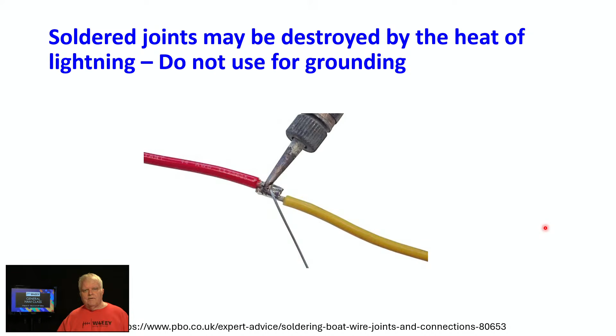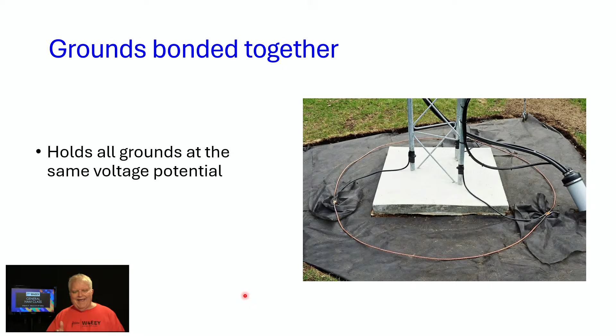Grounds bonded together. Here we have a three-legged tower. Each of the legs goes out to a ground, and there's a ground ring, and they're all bonded together, and there are ground rods at least in 3 spots. We say you want to have a ground rod for each leg of the tower. And when you're going to interconnect them, the mechanical clamps are just fine because you tighten them down and they're not going to come loose.